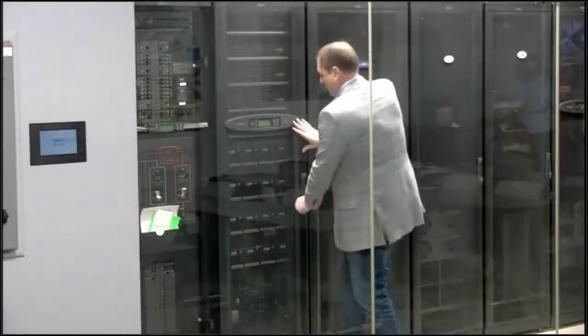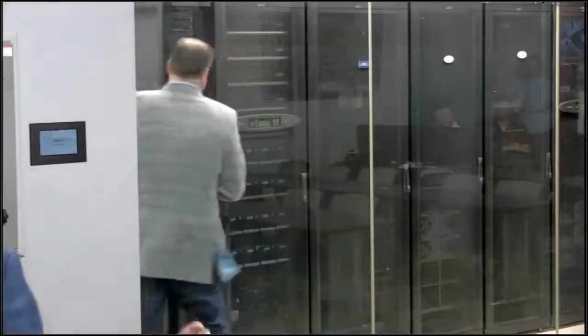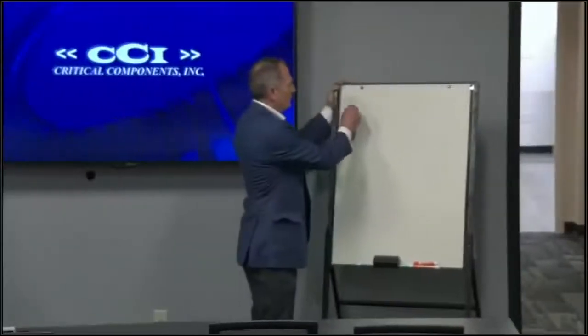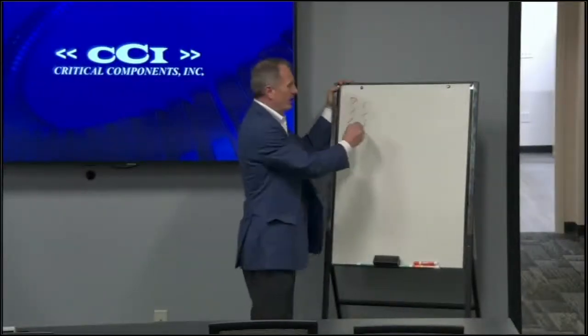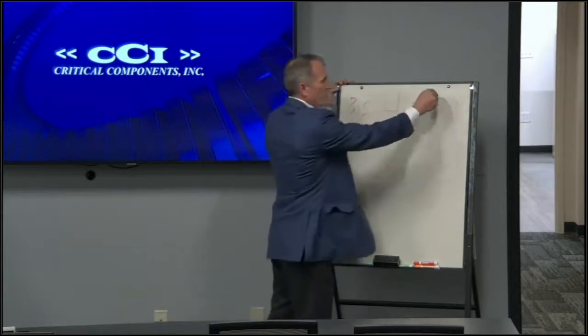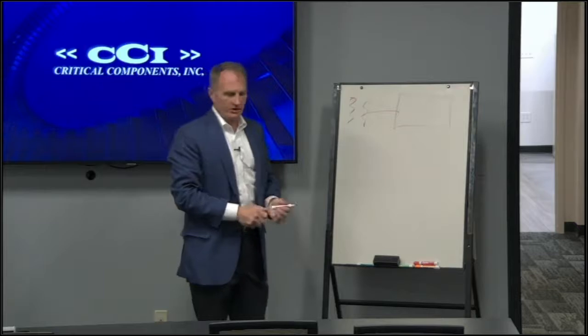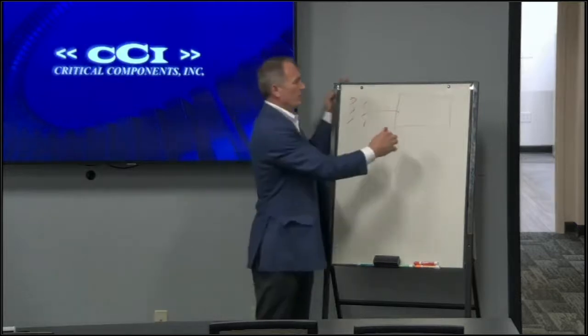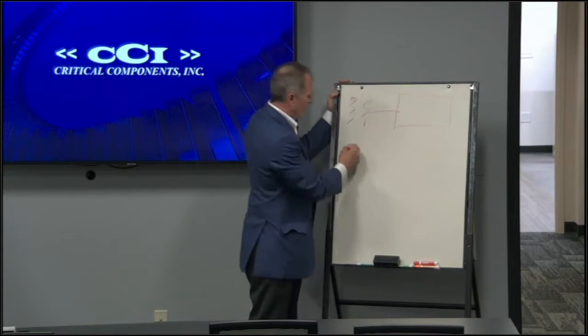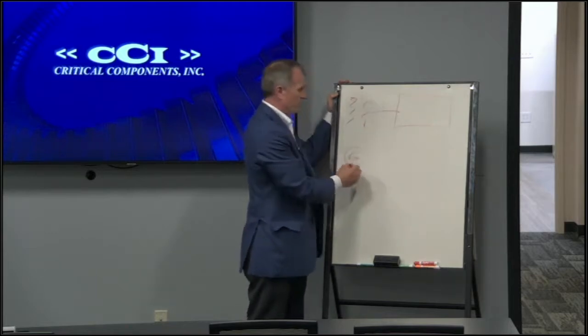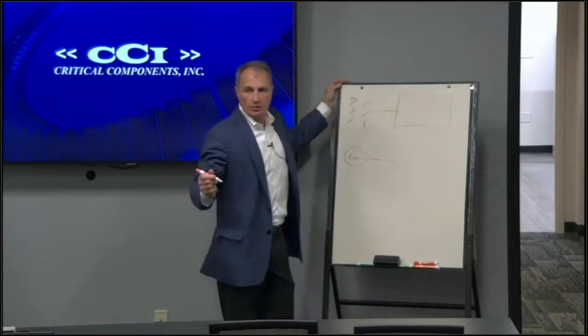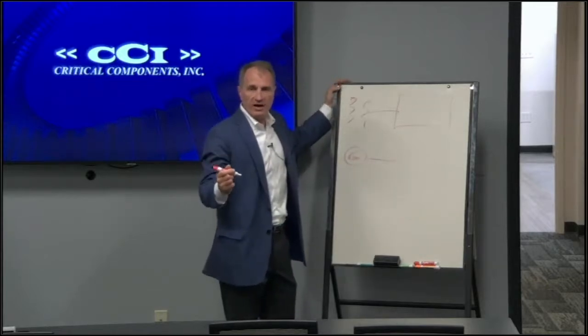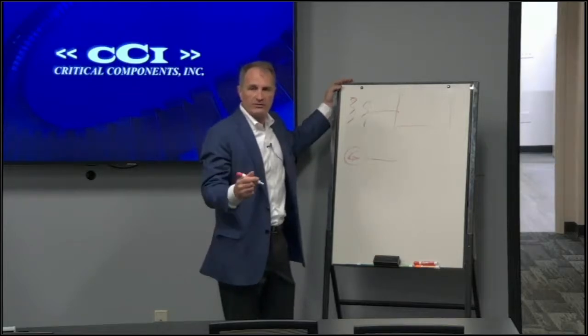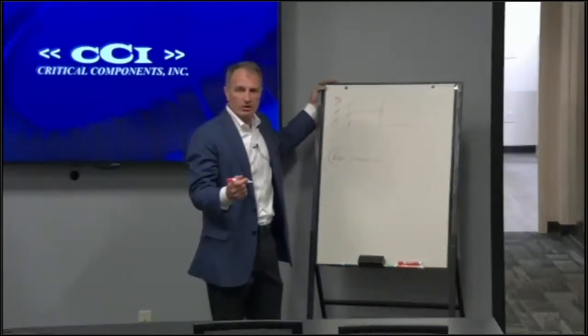As we had discussed, the UPS system is the heartbeat of the data center. The UPS system is fed from utility power, and utility power is usually designated as a transformer that would feed a main piece of switchgear. This switchgear is what will eventually feed the UPS system, but first we have to have a power generation plant to back up the UPS system. The UPS system has a finite amount of battery runtime, but the battery runtime is there to allow us to get the generators started as our redundancy and our backup to the utility.